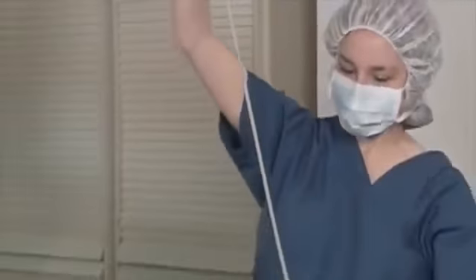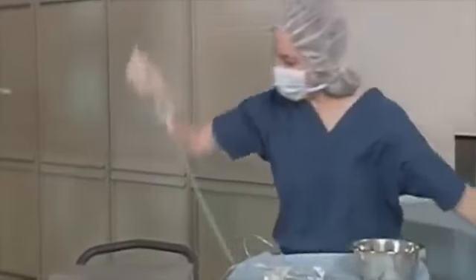Once this is done, the umbilical cable, which is not sterile and needs to be either draped or disinfected by wiping it with a 70% isopropyl alcohol dampened cloth, is connected to the controller. The red dot on the umbilical cable should point up as it is connected. Once again, you will hear a click as it is secured into place.